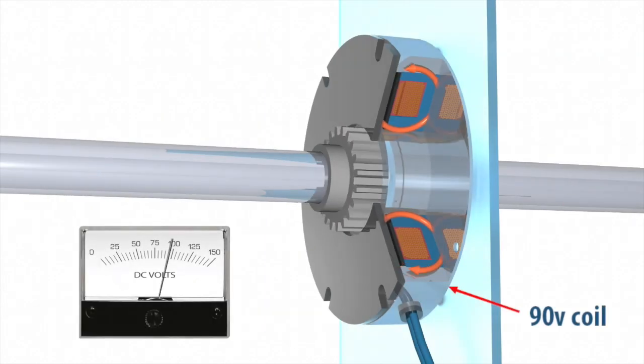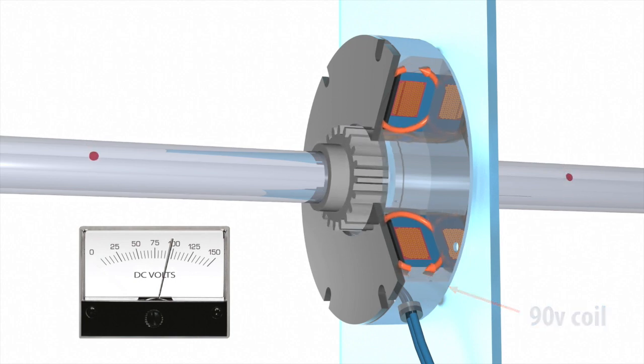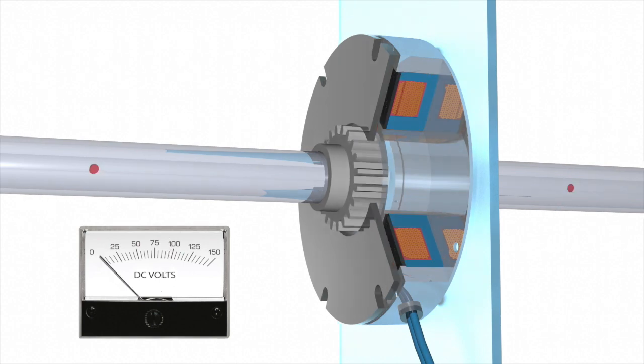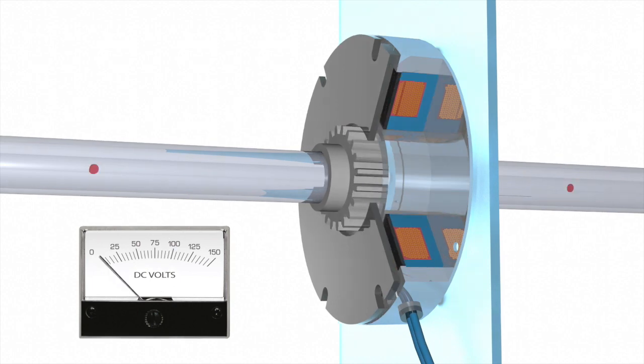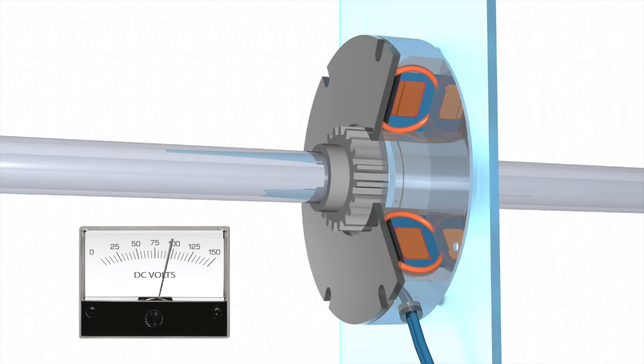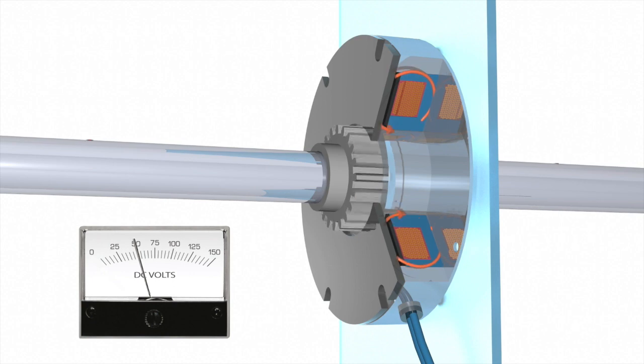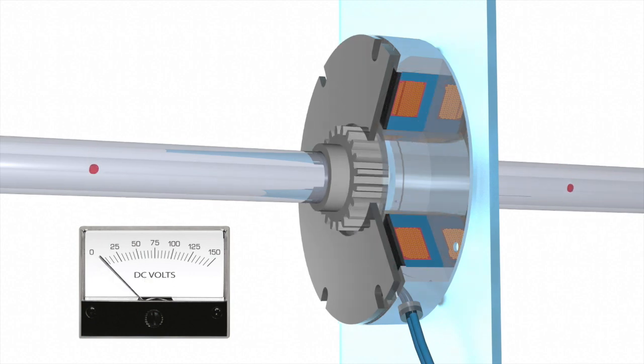Brake coils are normally 90 or 24 volts, but there is a wide variety of specialty voltages available. Different controls can also be used with holding brakes. Over-excitation can provide a faster response. For power savings, reduced current controls are available. Since most of the current is required to reach across the air gap to the pressure plate, once the pressure plate is engaged, current can be reduced significantly to reduce power consumption of the brake.